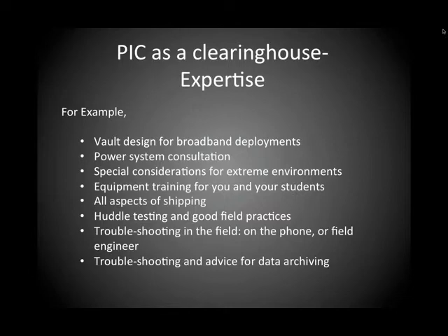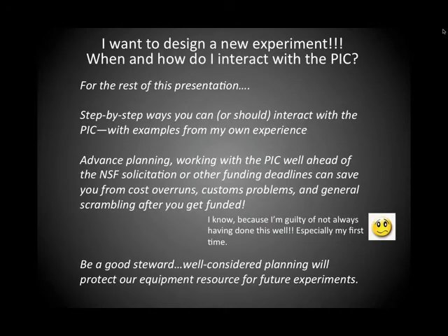An example of why that can be important is that in recent years, the seismological community has started to think, well, we really need a broadband instrument that we can actually directly bury in the ground instead of building a vault to house it. And so recently, the PIC worked with manufacturers to communicate that need and helped influence the design and function of a new direct bury instrument. And the PASSCAL Instrumentation Center, with the help and encouragement from the PASSCAL Standing Committee, acquired the funding to buy several of these, and we're going to be starting to work with them and test them out in the coming years. So that's an example of where the community or a few people bring up an idea, and the PIC can help us make that happen because they have the ear of the manufacturers. So do speak up if you have an idea.